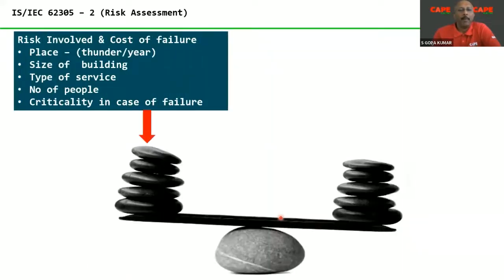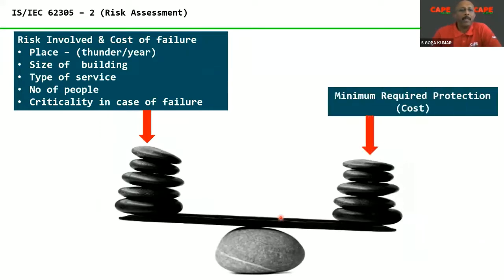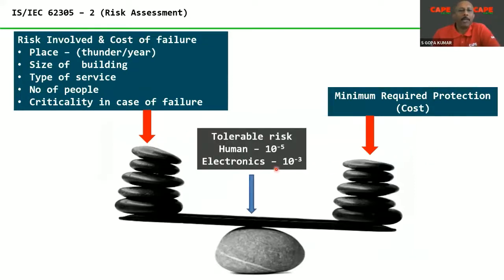So basically there are two energy wave shapes. Risk assessment, the second part of lightning protection, is covered in IS 62305 part 2. Risk assessment is a technique with which the risk involved in a building is calculated. For example, it depends upon the place where your building is located, the number of thunderstorm days per year, the size of the building, type of service, number of people, and criticality in case of failure. And then the standard gives you a tolerable level. Tolerable level means up to what level you can have safety.